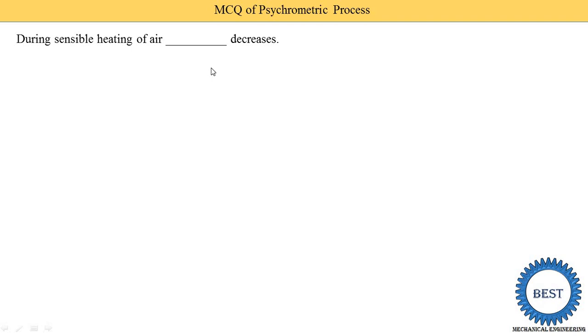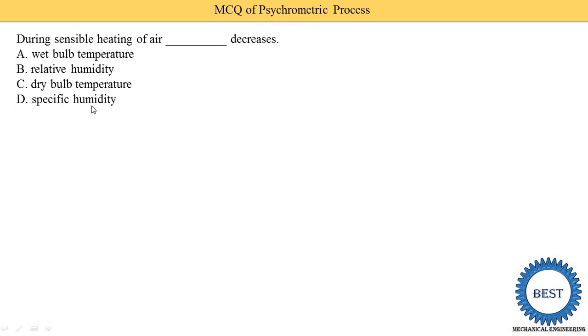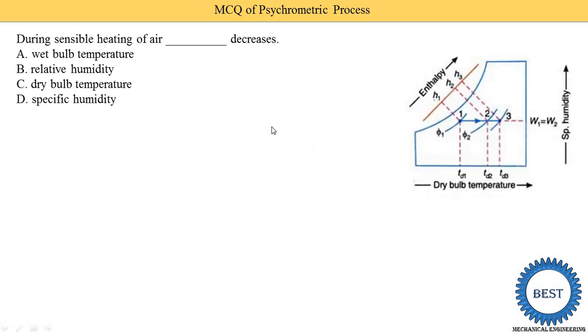During sensible heating of air, which parameter decreases? During sensible heating, the dry bulb temperature is increased and specific humidity remains constant. To solve psychrometric process MCQs, you at least need to draw a psychrometric chart. Here we see the inlet air, the heating coil, and the outlet. Dry bulb temperature increases, wet bulb temperature also increases, and specific humidity remains constant. The relative humidity is higher at inlet and lower at outlet. So option B — relative humidity decreases during sensible heating — wait, actually relative humidity decreases.